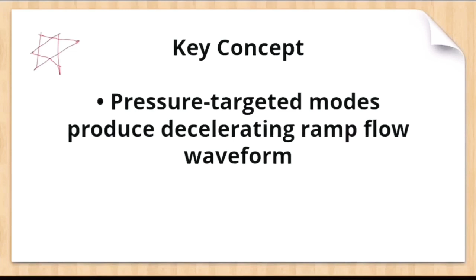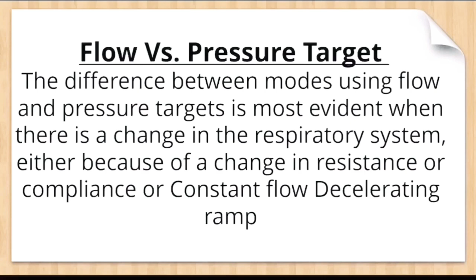Okay. Now, flow versus pressure target. The difference between the modes using flow and pressure target is most evident when there is a change in the respiratory system, either because of change in the resistance or compliance. Now, if there is a change in the respiratory system, the respiratory system will behave differently. The parameters will be different when either we have selected flow as a target or we have selected pressure as the target. Now, to illustrate, when a change in respiratory system occurs, the set target variable remains unchanged.